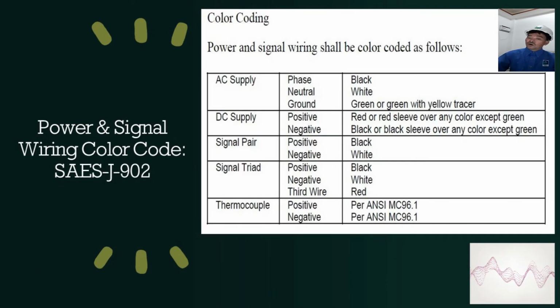So we have the standard color coding. Power and control signal wiring shall be color coded as follows. For the AC supply, phase is black, neutral is white, ground green or green with yellow tracer. For the DC, positive is red or red sleeve or any other color except green. Negative will be black or black sleeve or any other color except green. So for the signal, positive is black, negative is white. For the signal triad, positive is black, negative white, and the third wire is red. So for the thermocouple, the color coding will be as per ANSI MC 96.1. So these are the standard color coding of the power and signal wiring.